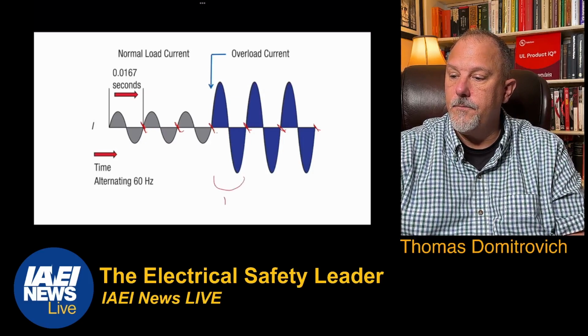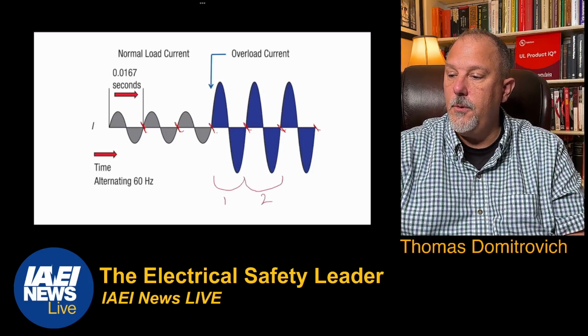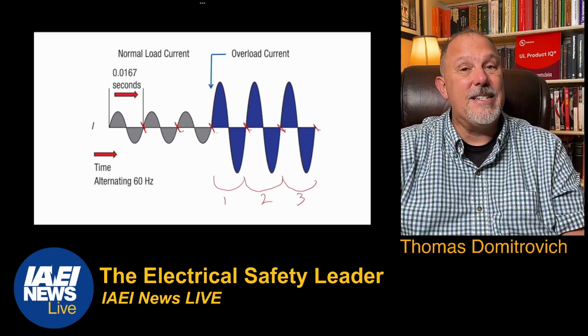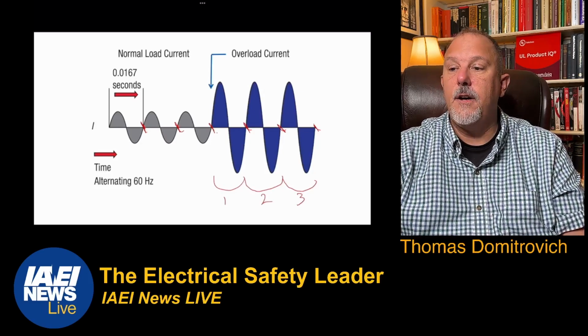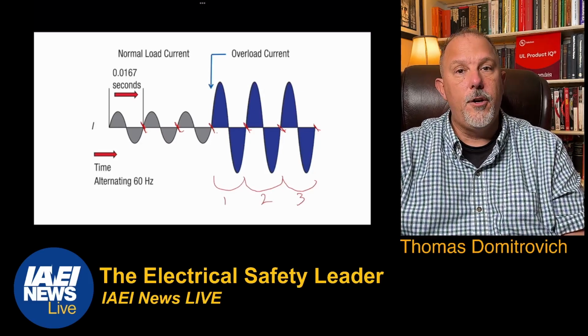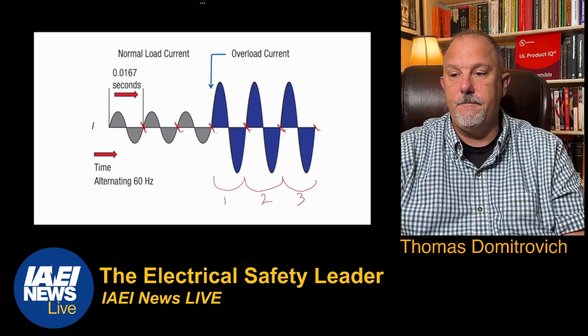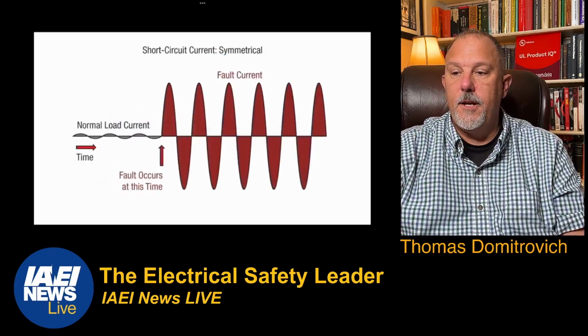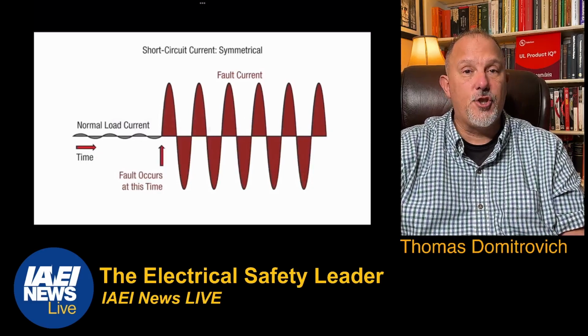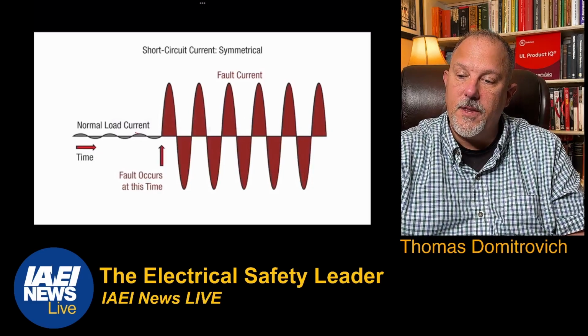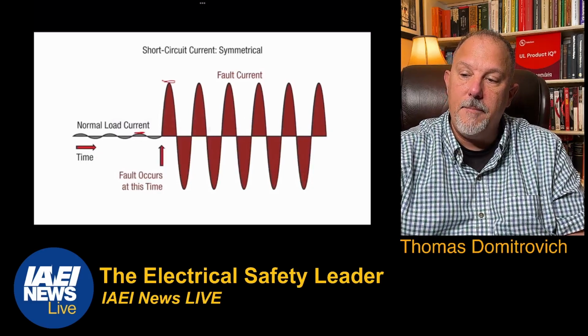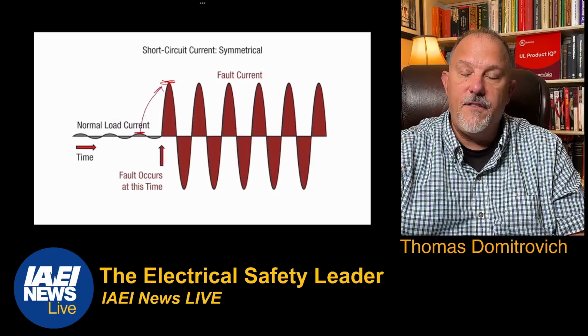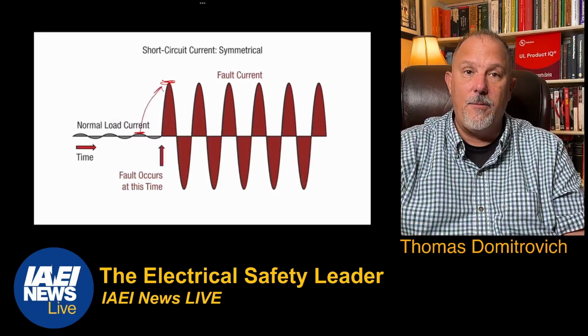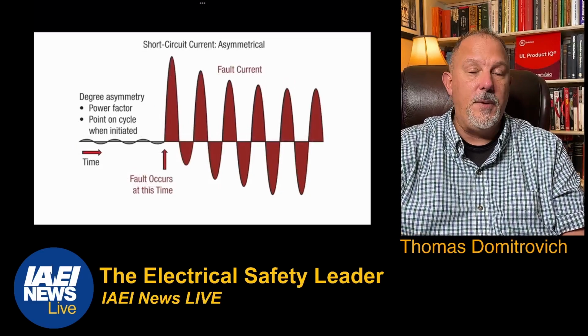1, 2, 3 cycles of an overload on that circuit. This is an example of a short circuit. You can see the difference between the magnitude of current here and the magnitude of current there. Very large difference. And if I would draw this correctly, it should be asymmetrical.